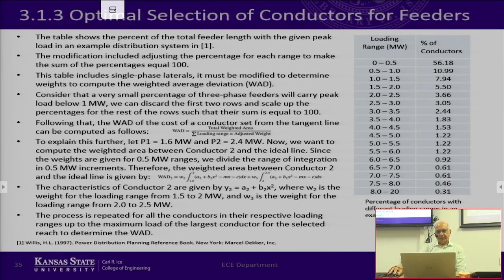So we need to bring the smaller conductors as close as possible to the lower line. The larger conductors, since there are only few of those, even if you don't do a very good job selecting them, your losses won't be that significant. But the smaller conductors need more attention because there are more of them in the system compared to the larger ones.